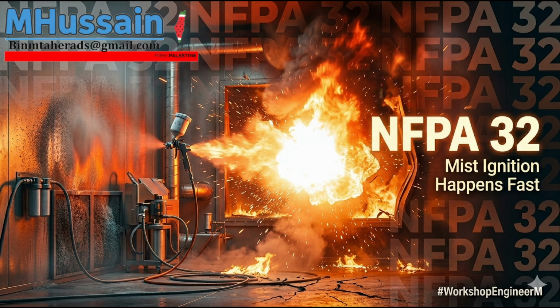And when subjected to the high heat of a commercial gas dryer, those residual oils undergo oxidation. And oxidation is an exothermic reaction. Right, it produces its own heat. Now, while the dryer is tumbling and the blower is running, that heat is exhausted out of the building safely. But what if the cycle ends and the clothes just sit there?